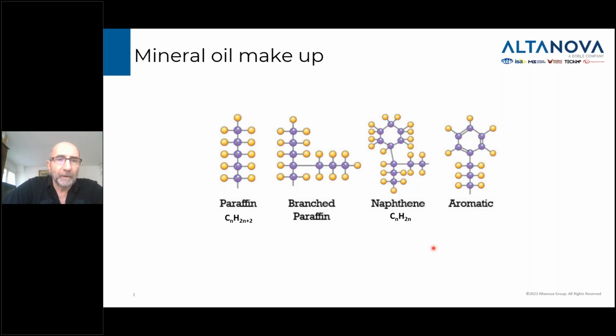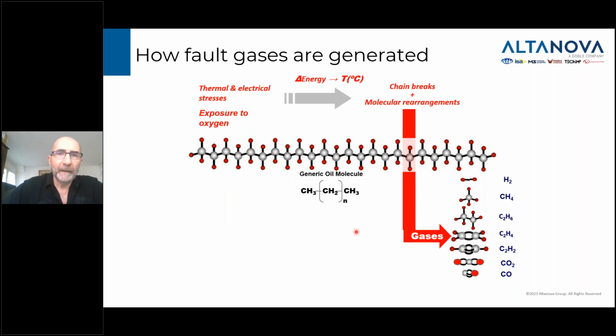The majority of them are what we call linear chemical form, like this one, where you have carbon atoms that are attached to each other, and hydrogen on the extremities. But mineral oil also has different configurations, either what we call branched or mostly aromatic. But overall, all those mineral oils behave mostly the same way when they're subject to a thermal fault or an electrical fault. So what happens in your transformers? Well, as your transformer is energized, the electrical and thermal stress energy start breaking the connection between the hydrogen atom and the carbon atom. That chemical connection is usually very, very weak, so it's very easy to break that connection.